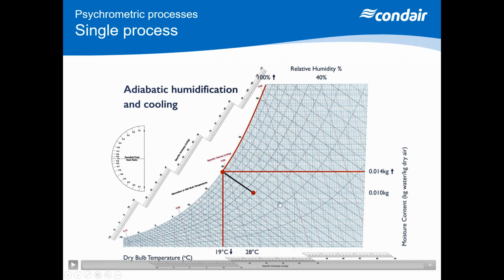So as we're evaporating water into the airflow, changing its state from a liquid into a gas, we're sucking heat energy out of the air. It's cooling. So the effect on the psychrometric chart shows us that we get an increase in relative humidity, that's 40, 50, 60, 70, and so on. There's an increase in moisture content, shown in kilograms per kilogram of dry air, but I also get a reduction in dry bulb temperature. I am cooling.